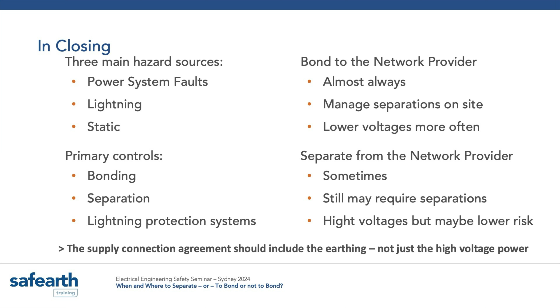Obviously our primary controls are bonding and separating, trying to manage lightning risks and all of our earthing risks. Bonding to the network earthing provider should almost always happen. In 20 years, I've never once assessed a transfer risk from a supplying zone sub down through an earth wire or cable screen that's actually been a problem - never, ever. So when you sit down with them for a new 66 kV connection, say straight away that we want to bond the earthing together unless they can tell us it's not a good idea. It should be that way around, not the other.